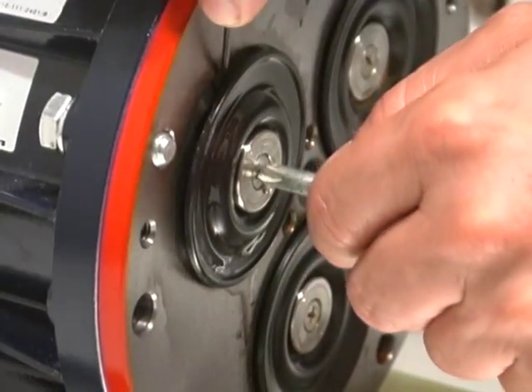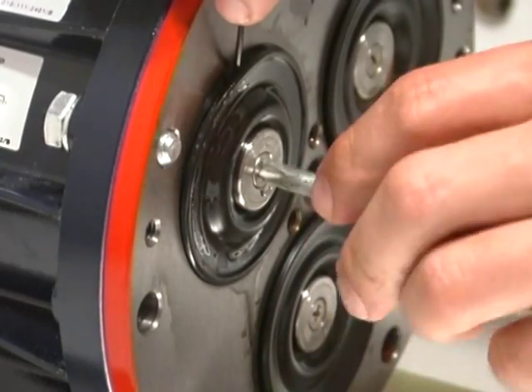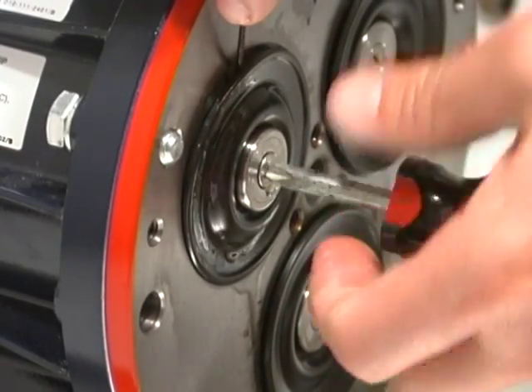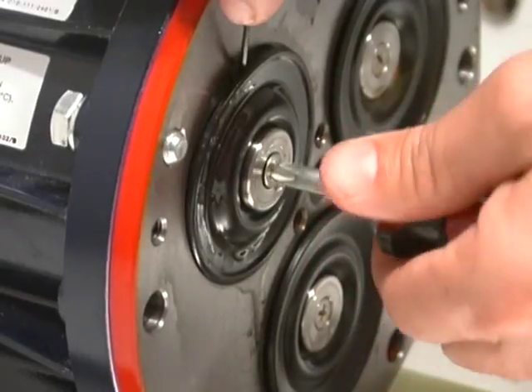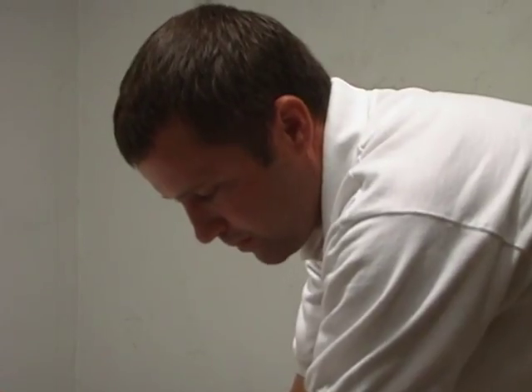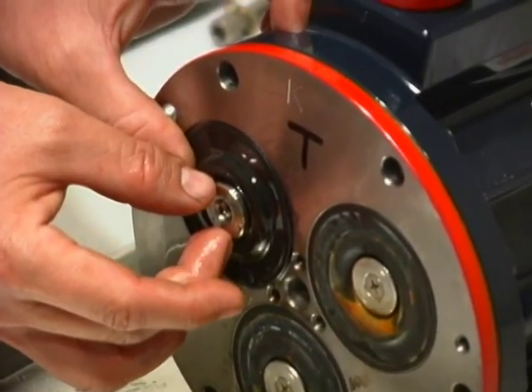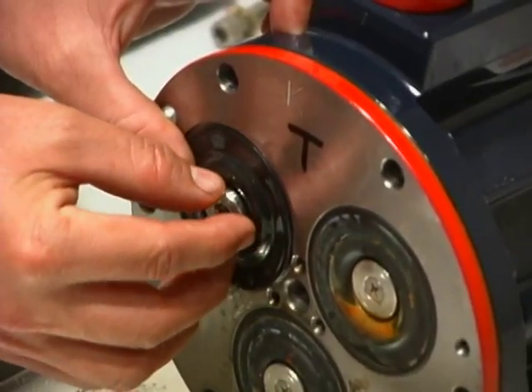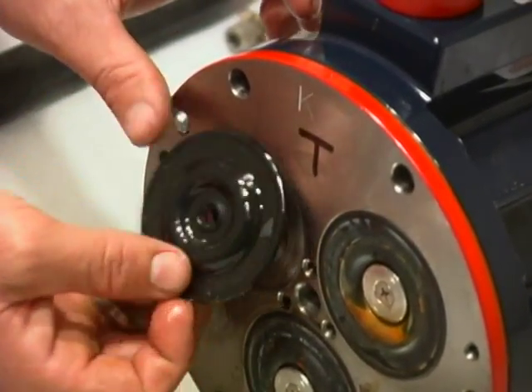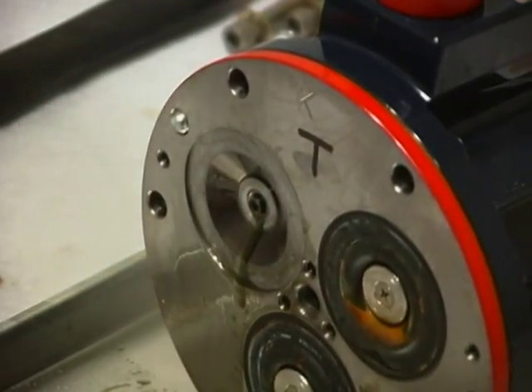If the diaphragms are bad and are being thrown away, grab the diaphragm with a pair of pliers and pull them away from the pump. In order to replace the diaphragm, the follower that holds it in place needs to be removed. This completes the removal of the manifold and valve plate from the pump housing.